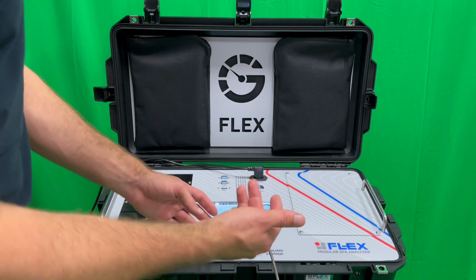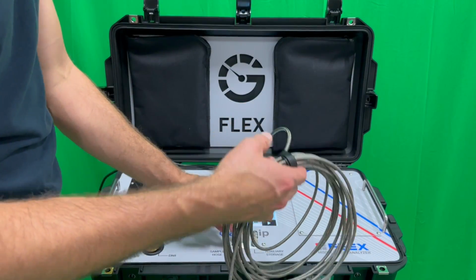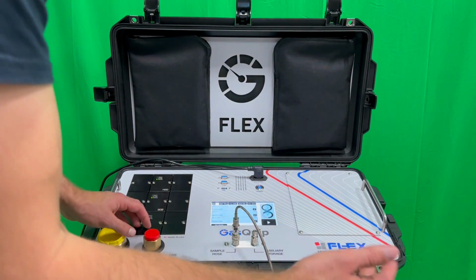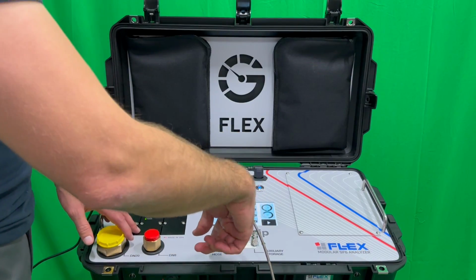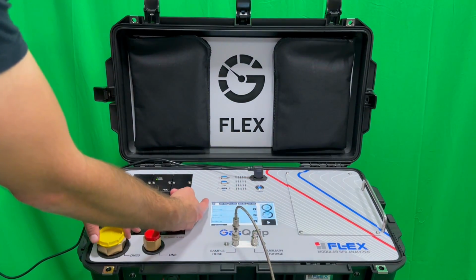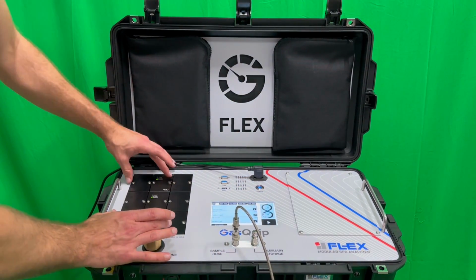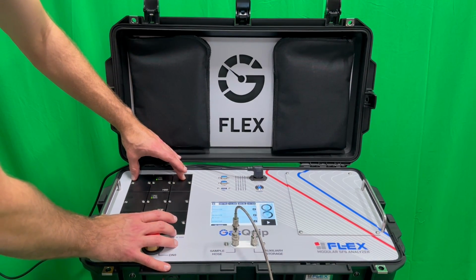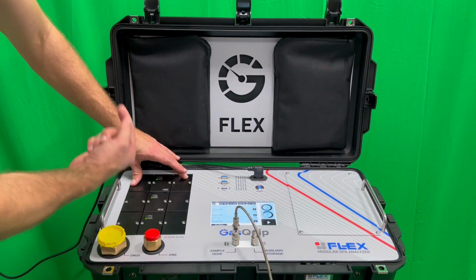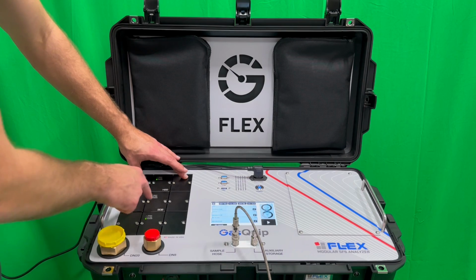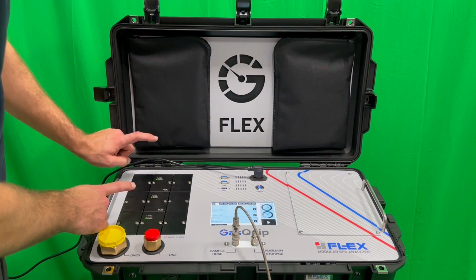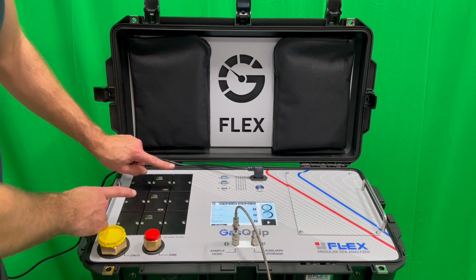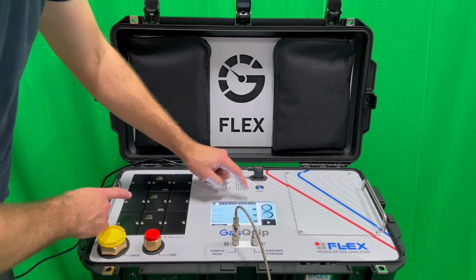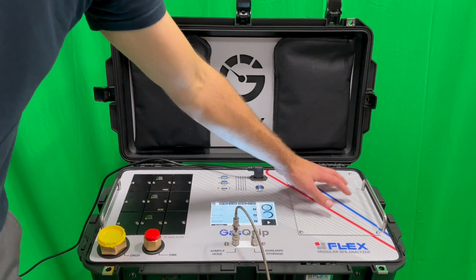The gas comes in through this hose from the circuit breaker, from the gas compartment, goes in through a manifold here, and a regulator steps the pressure down. Underneath these modules is a little manifold, and a solenoid will open up for each sensor module. Gas runs in and up through the sensor and then out to our internal gas recovery bag.